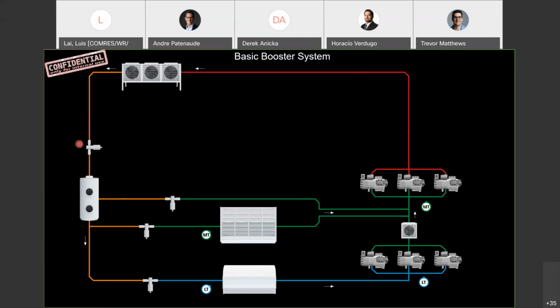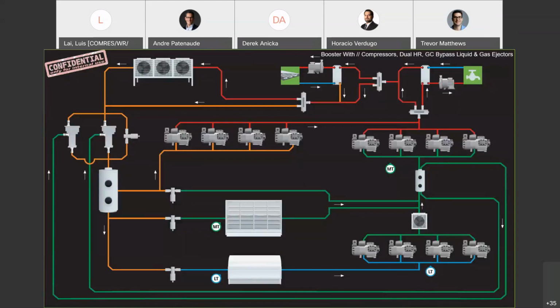They can also manage a bypass, a high pressure valve and bypass valve from a simple system perspective. As you start adding complexity, it's the same basic architecture, same basic system. Now, we can still handle 12 low temp, 12 medium temp, but now we can have one stage of heat reclaim. And when you come out of that heat reclaim coil, if you want to continue to heat reclaim with something else, then there's a second stage of heat reclaim, whether in series or whether in parallel, it doesn't matter.